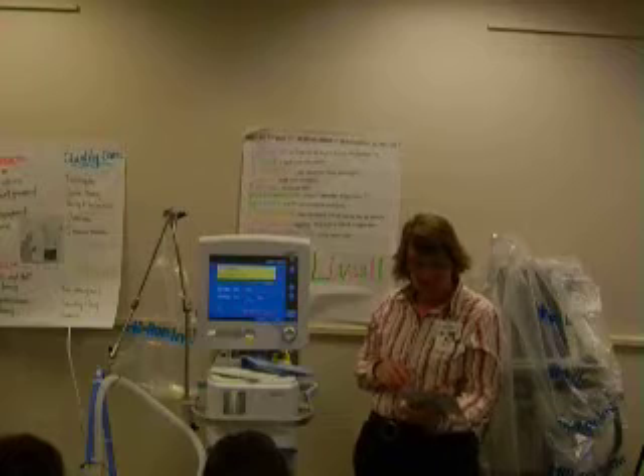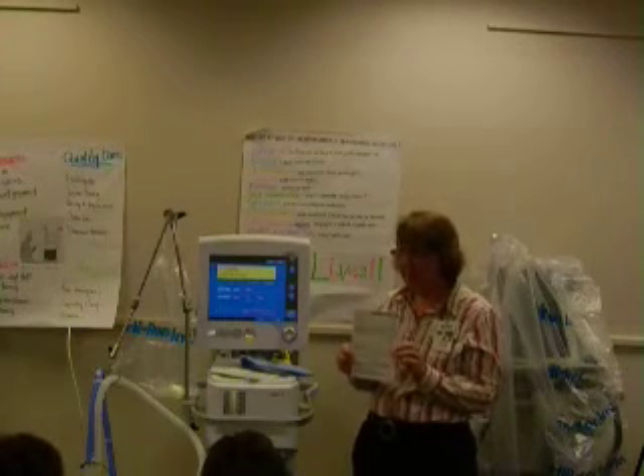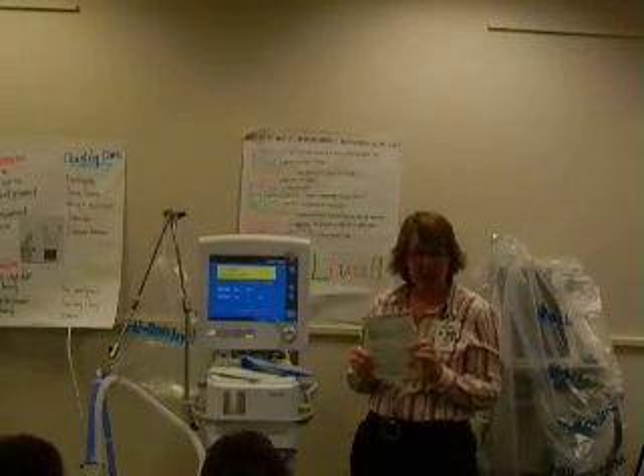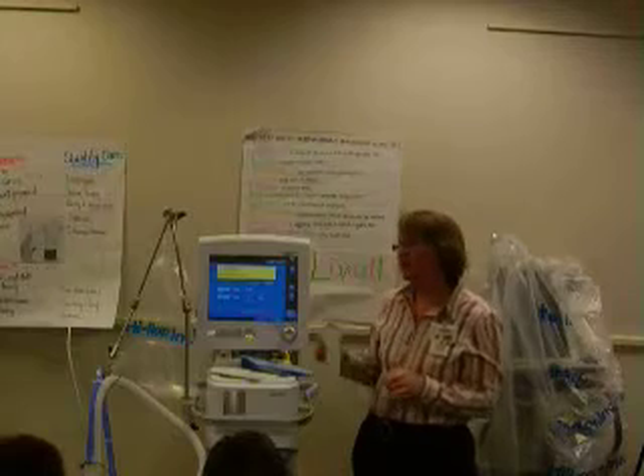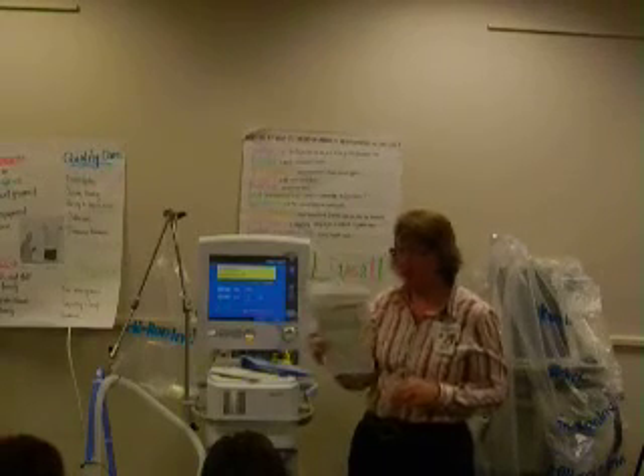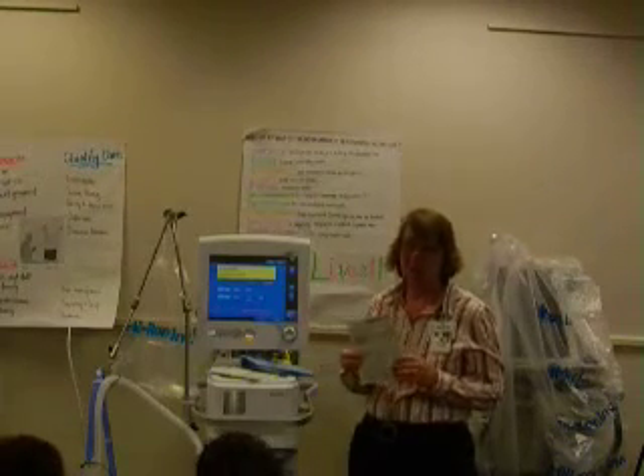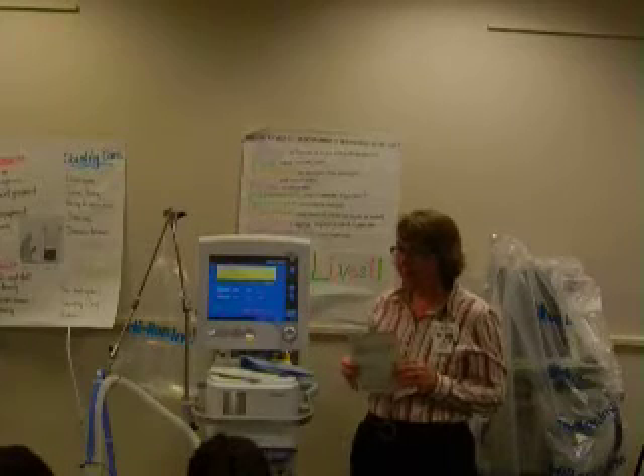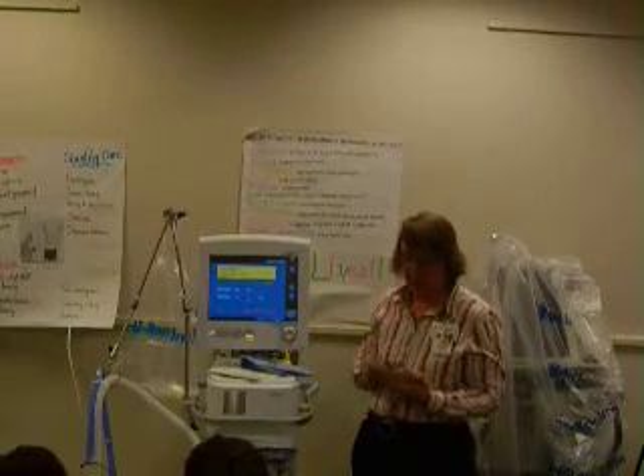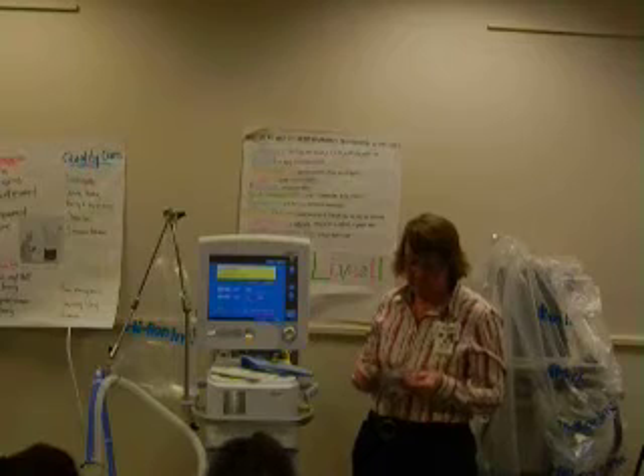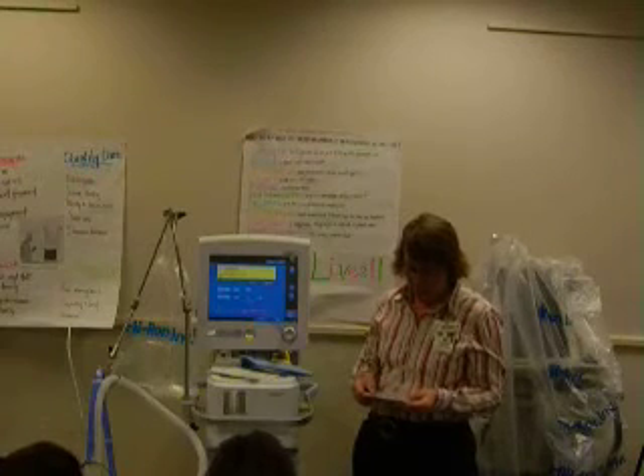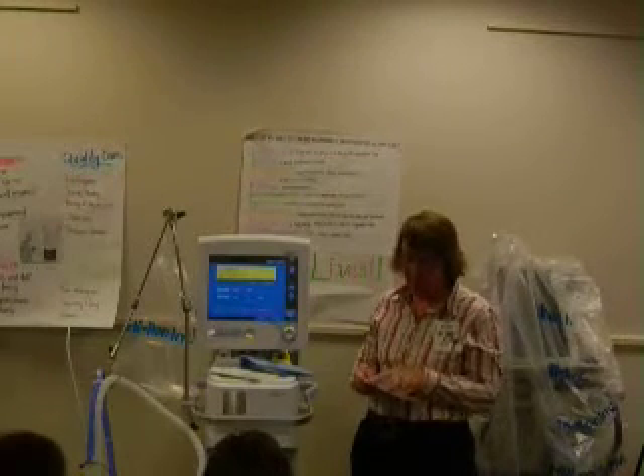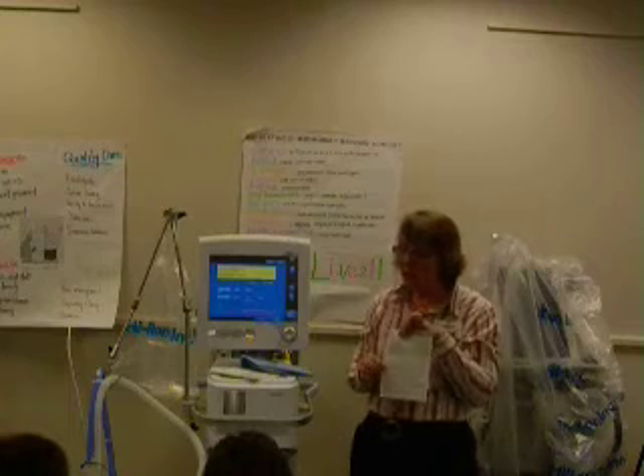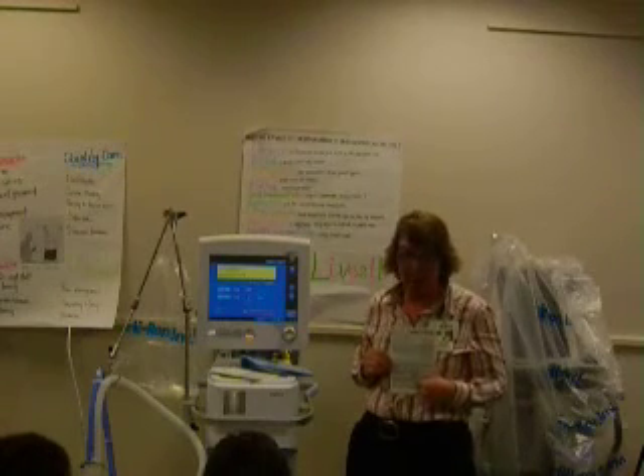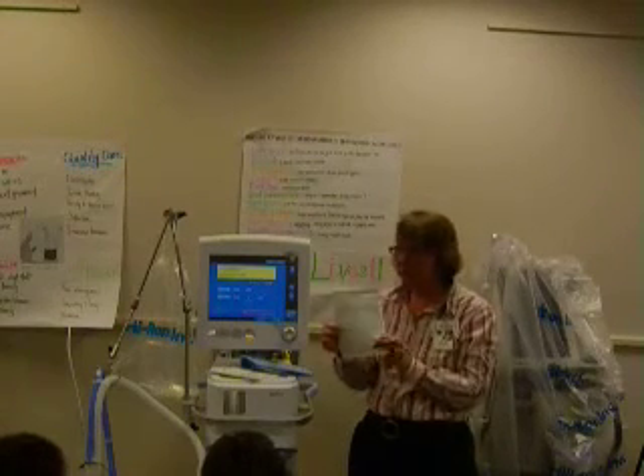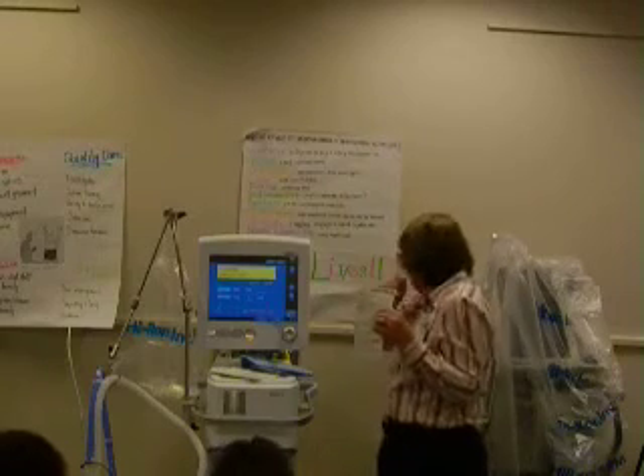So we're going to start. You don't have to memorize every little thing on here. What you do have to know is that when you come to calibrate the Galileo, you need this card and you have to do all the steps on the card. I'm going to ask you what steps you did as part of the calibration. On this card it says do or observe, then you verify and note. Column 1 tells you what you're going to do, column 2 tells you what will happen. You're free to make copies of this for yourself.